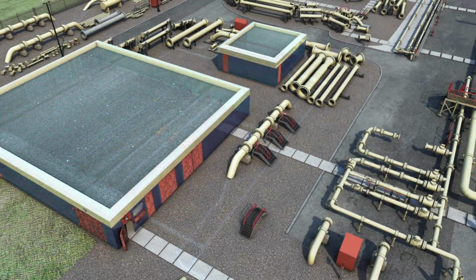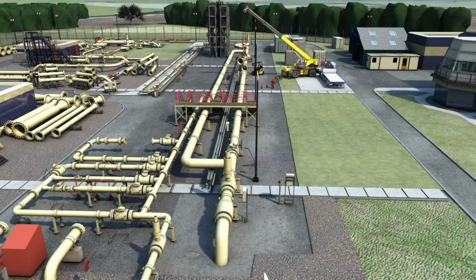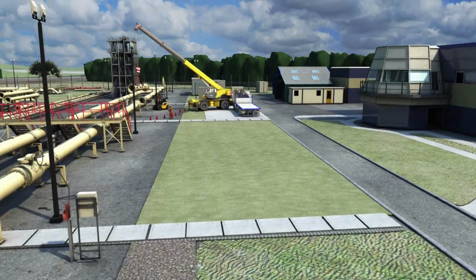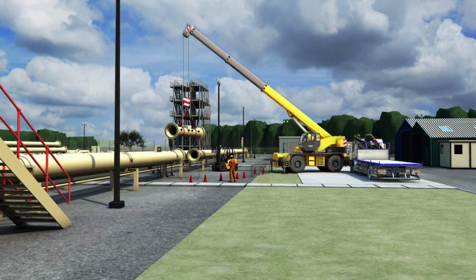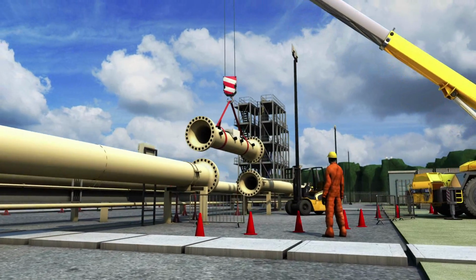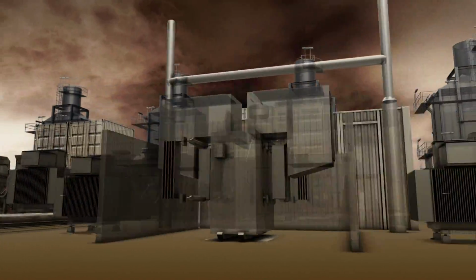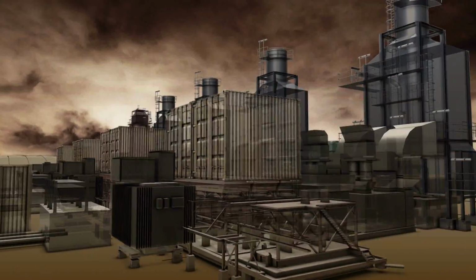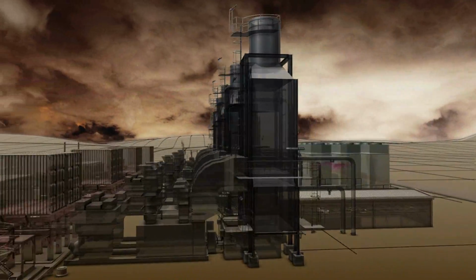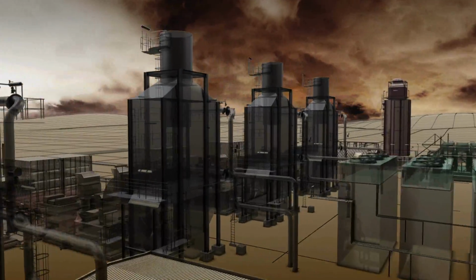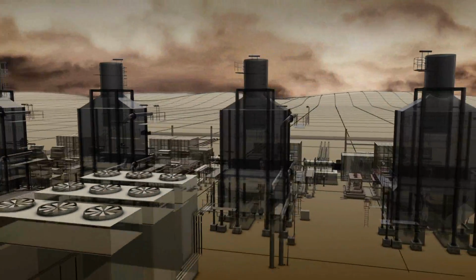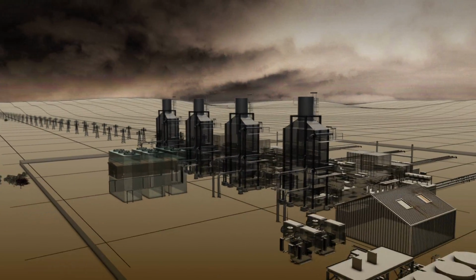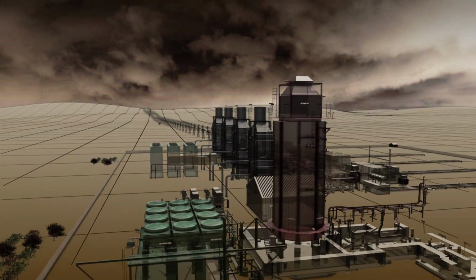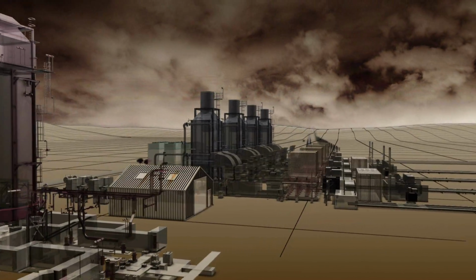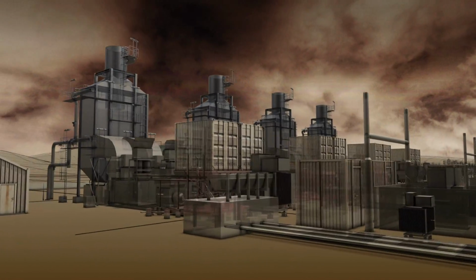The primary task routinely carried out on site is the calibration of meters of all types and sizes at pressures between 38 and 60 bar, often replicating complex operational pipe geometries. The GL Noble Denton Flow Centre has extensive experience of handling large diameter meters, such as a key custody transfer meter. Measuring gas into a power station is a situation where the accuracy of measurement is critical. The cost of calibration is insignificant when compared to the losses that can potentially be incurred through mismeasurement.